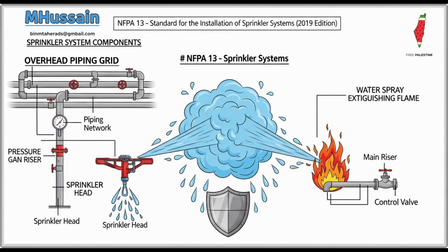But the crucial limitation, and this is a major compliance risk area, is that antifreeze solutions shall not be used in early suppression fast response ESFR systems, unless that specific ESFR sprinkler is explicitly listed for use with that specific solution. Why are ESFR systems so sensitive to antifreeze? What's the issue there? Well, ESFR sprinklers are designed for extremely high velocity, high momentum droplet delivery. Their goal is to achieve fire suppression, not just control.